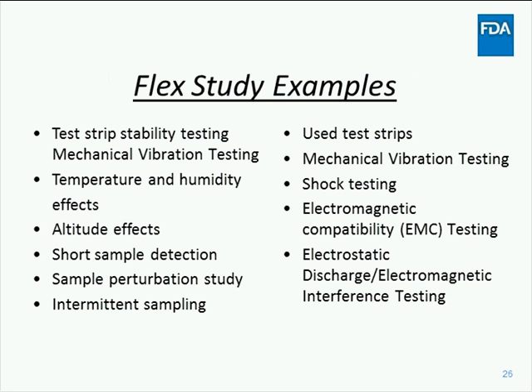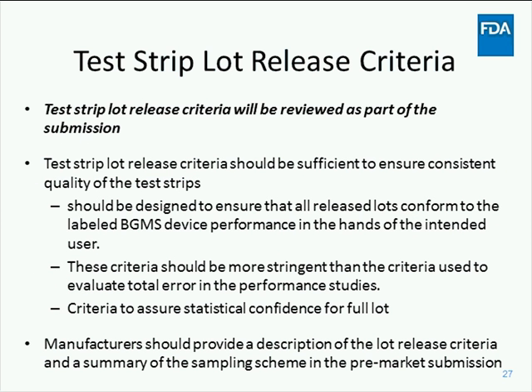This guidance document includes several examples of such flex studies, and some of them are listed here. So I'll highlight just a couple. Test strip stability should be established by assessing test strip performance throughout the claimed shelf life and conditions. The effects of temperature and humidity during device use should also be assessed. The use of used test strips or insufficient blood sample volume should also be assessed.